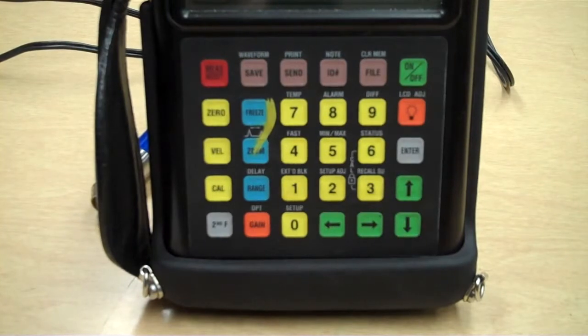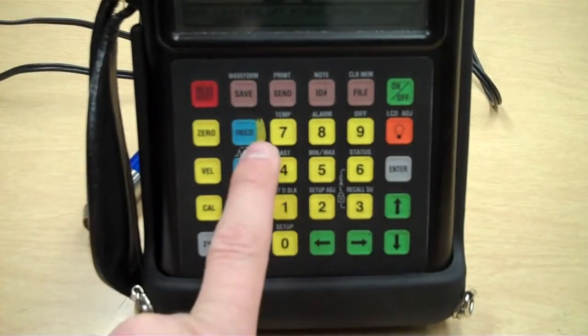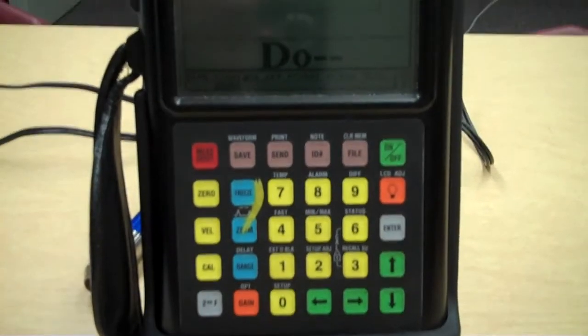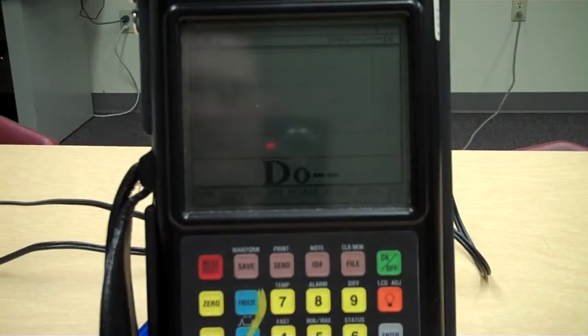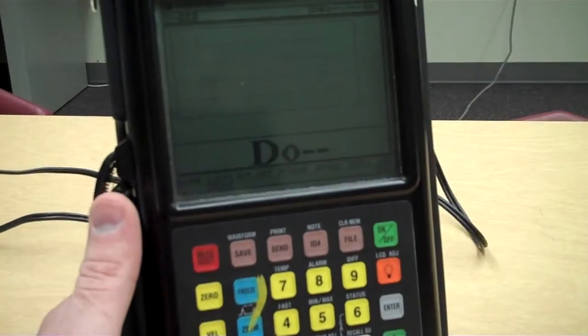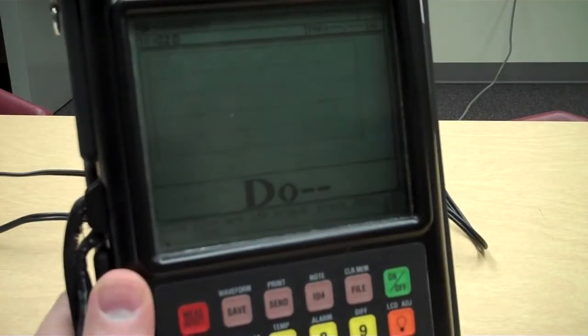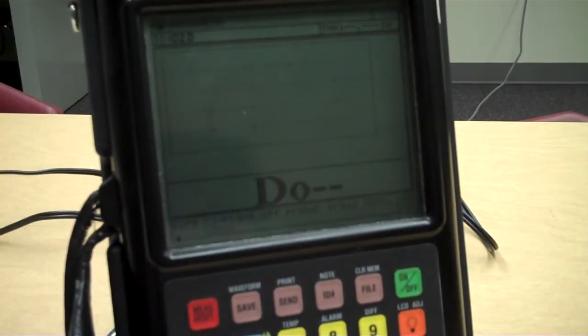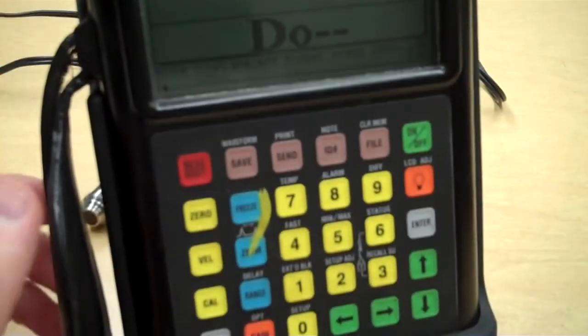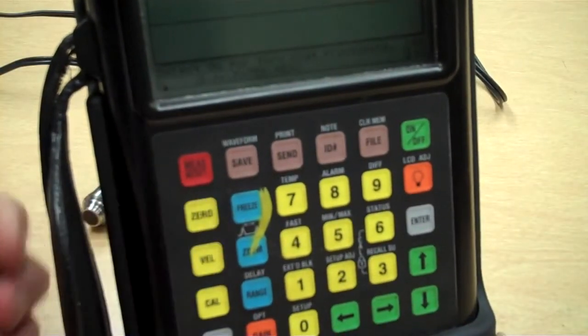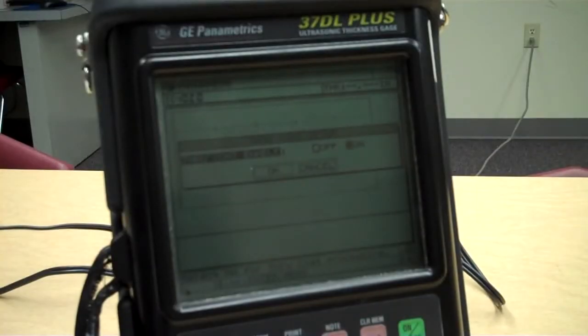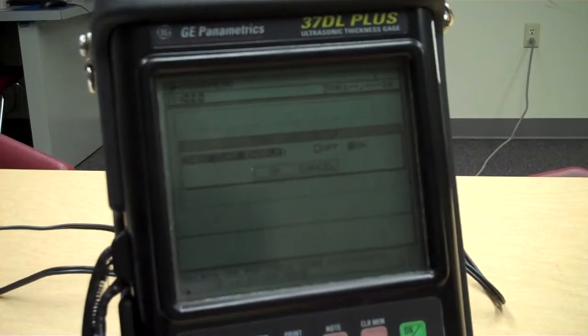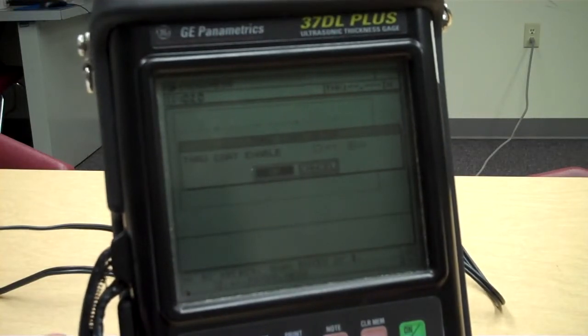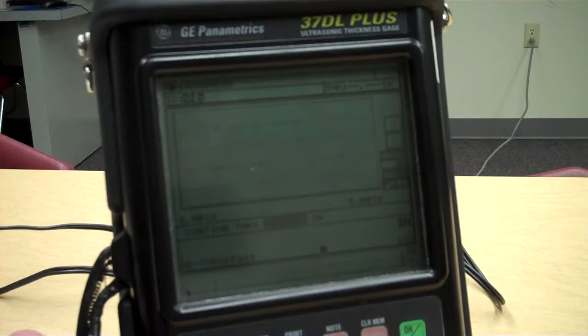Anyway, just give you a quick look at the 37DL Plus. Got a little bit of a different screen or a keypad on it. Somebody got a little paint on there for us. There's the screen, and you can tell right now it says wipe off the couplant. Try and get the glare off of there. It says wipe off the couplant and press 0. So I come down here, press the word 0 like it told me to do. Then I come back up here and it says thru-coat enable. That allows us to test through paint. We're going to do that. Okay. Hit OK. It says it's doing a 0 calibration.